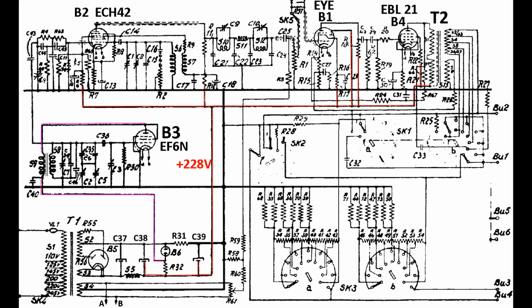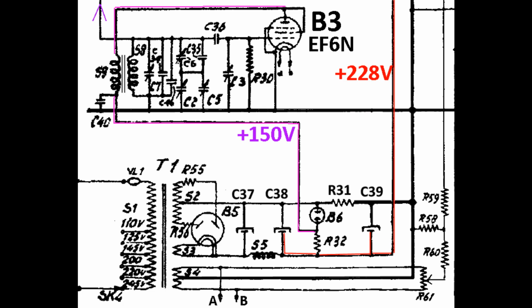If you follow this wire, the high voltage power to B3, you will see there are no local resistors in the anode system. There is only the series resistor to the B6 regulator tube, and that is already biasing B6 all the time to 150 volts. Also, you see the B3 tube is a pentode, coupled into triode mode. So this means the two steering grids are fully on, to anode voltage and to cathode voltage. So this turns on the tube completely. R30 is a 1 megaohm resistor to ground. So again, you turn the tube on completely. Full maximum potential current goes through this transformer.